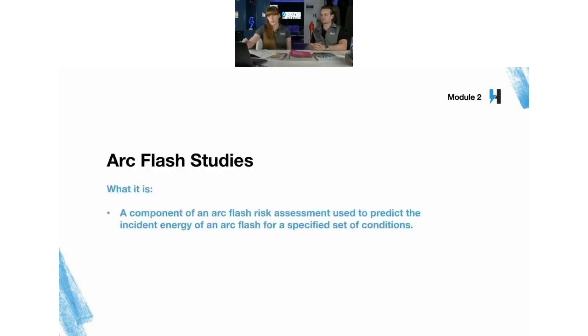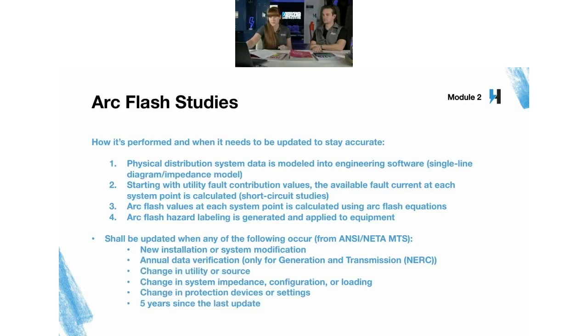All right, last but not least of the ones we're talking about today is the arc flash study. So it's a component of your arc flash risk assessment used to predict the incident energy of an arc flash for a specified set of conditions. So basically, it helps you identify how bad an arc flash hazard might be under a very specific set of conditions, though, because again, it's reliant on that data being accurate that you've fed into the model for the calculations.